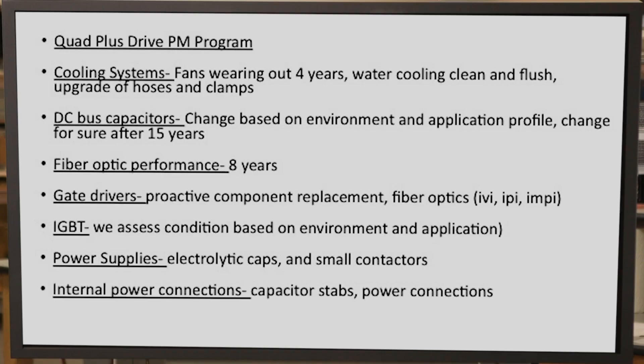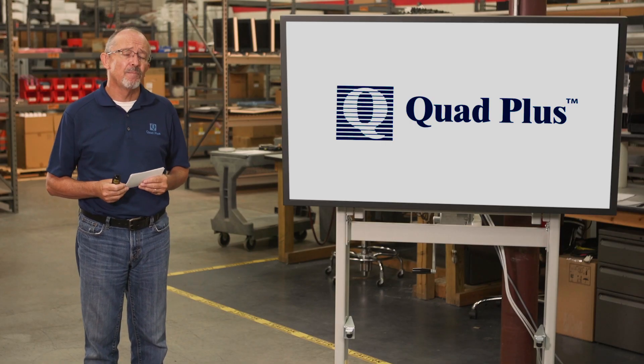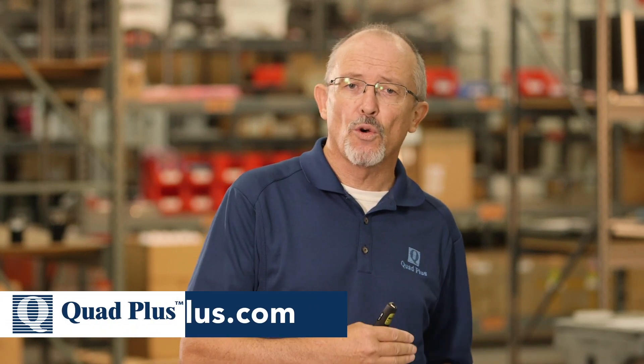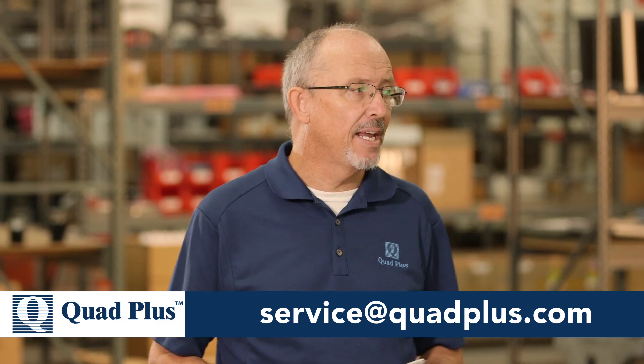On the internal power connections, there are connections in behind that aren't visible from the front of the unit. We know where to look and what to do in order to remanufacture and recondition those to improve reliability. Another strategy to consider is replacing units one at a time. If you have a lineup or several units, there are a number of advantages: you can defray the cost and do this retrofit on your OPEX budget, not your CAPEX budget. Another big advantage is that for displaced units, we can remanufacture them — now you have a functional spare on the shelf. As you move forward on your program, you actually have more and more capability to support the units remaining in service.